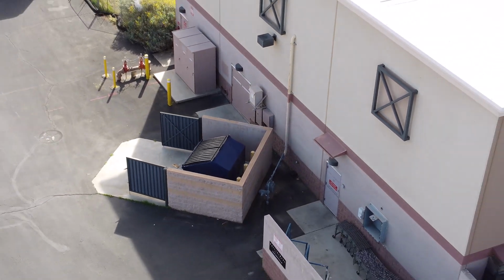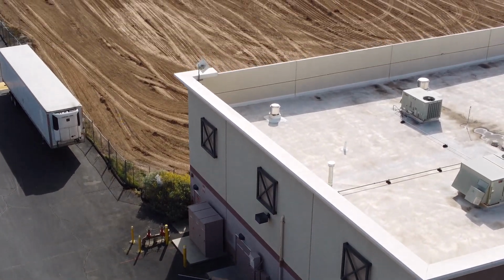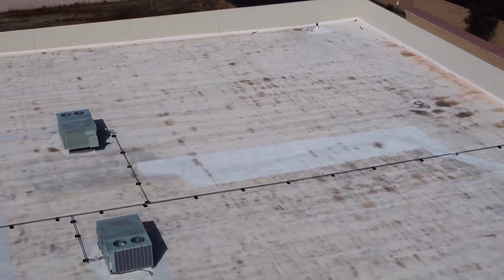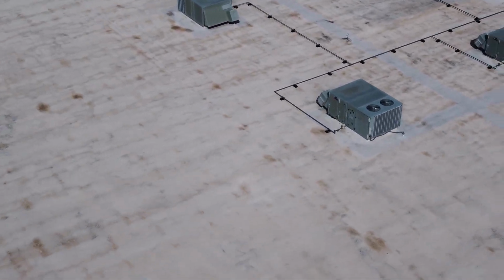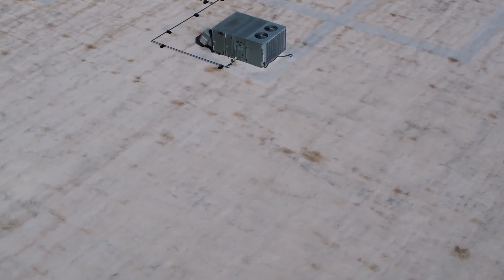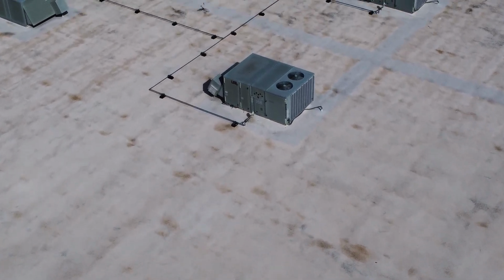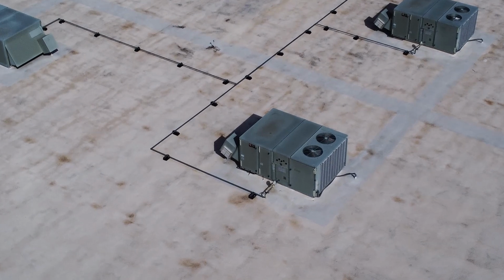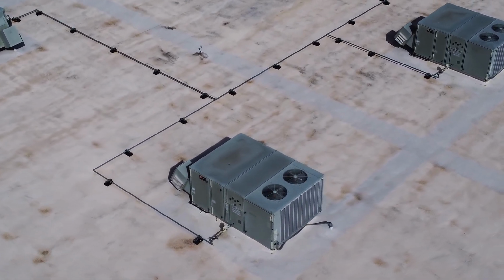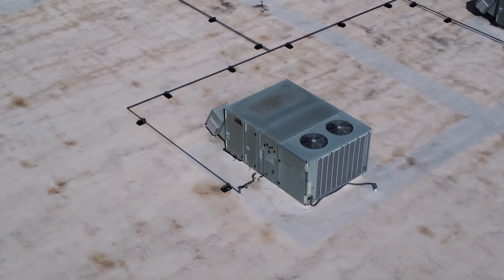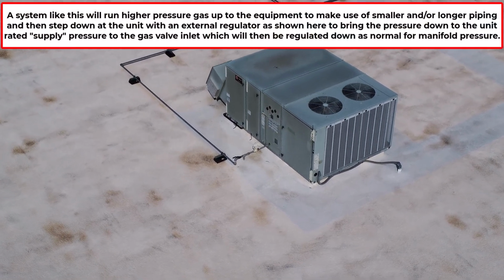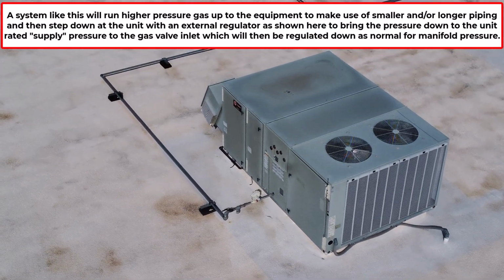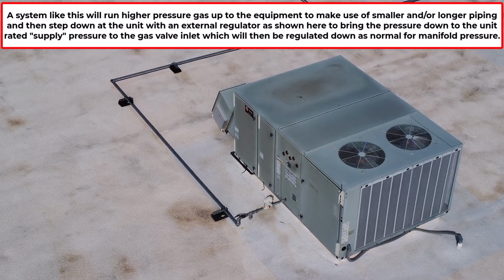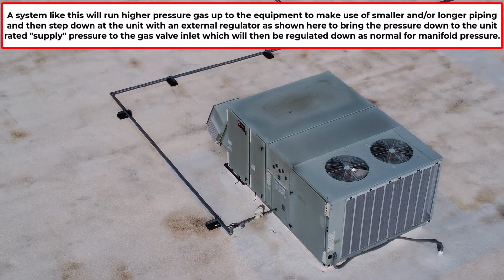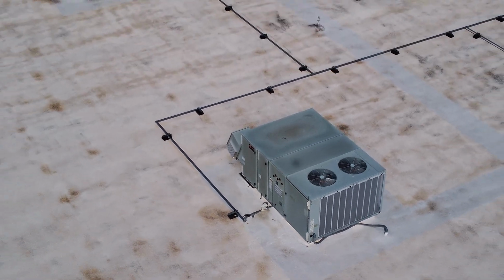So let's see, is that one of the high pressure systems that has a regulator on each unit? That's how some stores do it, so they can get adequate gas flow or volume: set the pressure higher and then put a secondary step-down at each unit. I think that's what they do here. Those get you to your acceptable range between your max and minimum connected supply gas pressure. It could be like 5 inches or whatever for natural gas, and then you're usually stepping it down. A lot of units are 3.5 inches at the manifold.